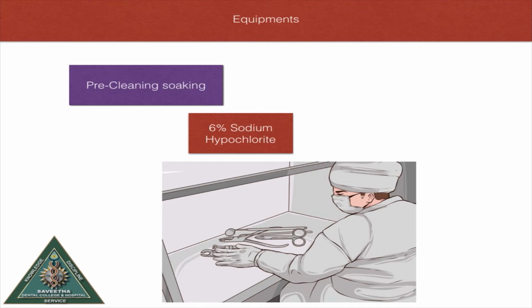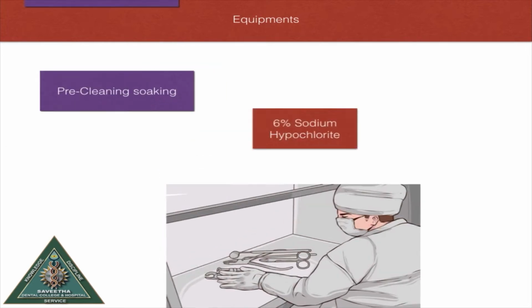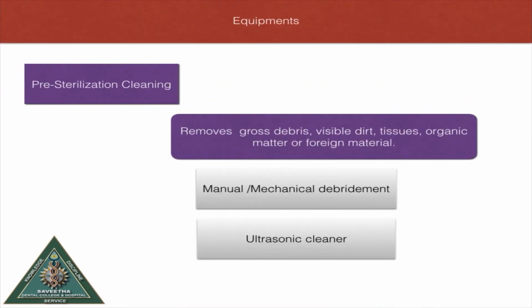Pre-cleaning soaking is usually done by immersing the instrument in 6% sodium hypochlorite solution immediately after use on a patient. It is done for about 30 to 40 minutes. This process reduces the microbial load on the instruments. After this, the instrument is subjected to pre-sterilization cleaning.